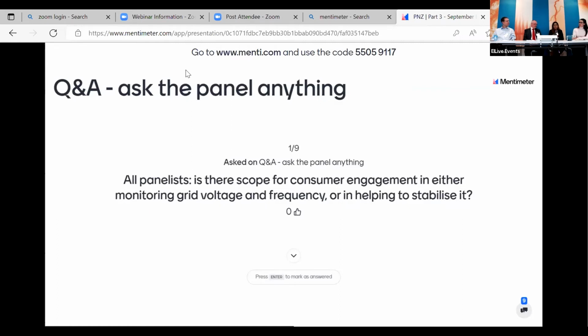We've already referred to oscillations in Scotland happening right now, but there's no grid code addressing oscillations and what inverters are supposed to do, except for the grid-forming part, which isn't mandatory, during fault ride-through when oscillations happen. A grid code can help, because if you understand how the system will behave in the future, you can define mitigation measures regardless of technology—generation, converter models and software, or even synchronous generation can help mitigate it. The grid code is still lacking in defining this transient behavior, which is why connecting generation doesn't really know what it needs to do when it connects to the grid.